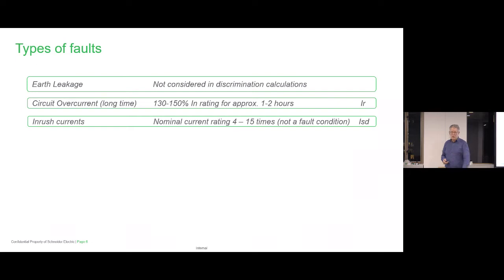There's another one which is called inrush current. Nominal current rating could be 4 to 15 times. And I've made a note there: not a fault condition. Not a fault condition means you've got loads that have inrush currents and you don't want the breaker to trip. So you need to know where to set that, and you've got to have a circuit breaker that has the ability to do that. So that's an important one. It's a fault that's there, but you don't want it to trip, but it can happen. And often if a breaker is tripping around this type of fault, it's because the selectivity has not been done. Someone's just put the breakers in and they're all set to minimums, and you've got a problem.